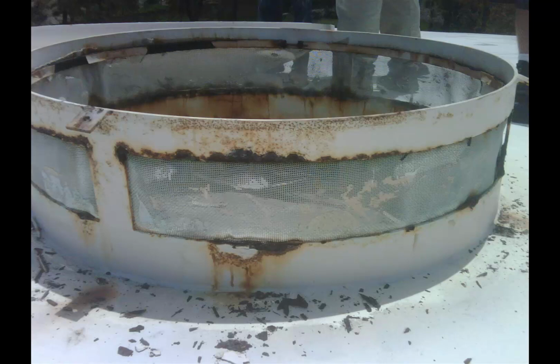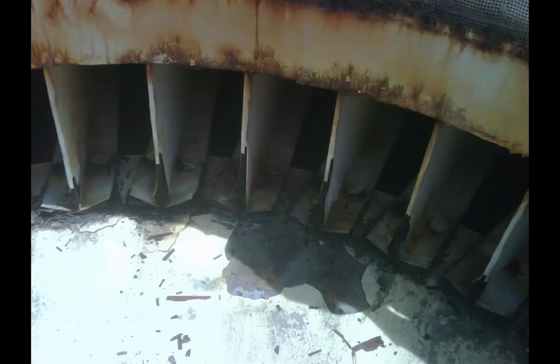One of the problems that we had not too long ago was with a vent on top of one of our reservoirs. We took it apart because we were going to do some coating work, and we were actually going to try and coat the top portion of that dollar plate. But as soon as we took the top off of this vent, one of the things we saw was the individual rafters that landed on it. And if you look closely, you can see that the structure of these beams is coming apart. I've never seen steel delaminate the way we saw on these beams. There were a lot of theories on what caused it, but all we knew is that we had a major structural issue with this tank and it could not be left alone.